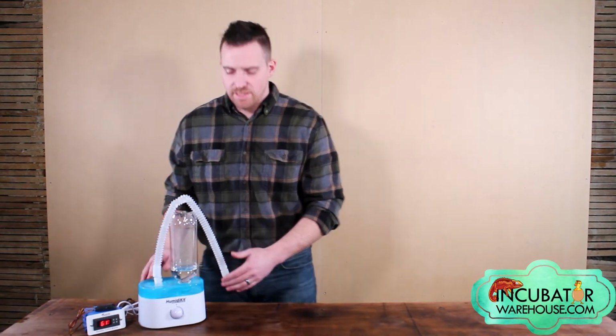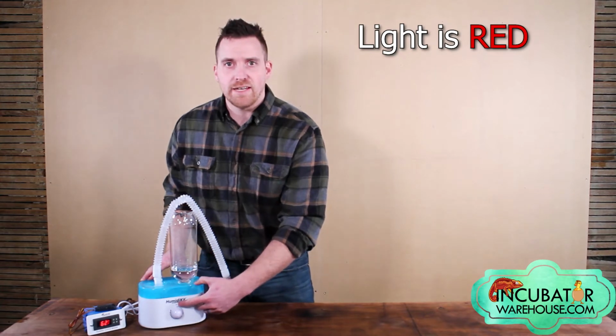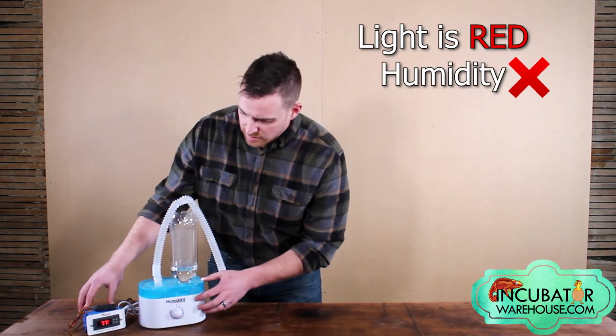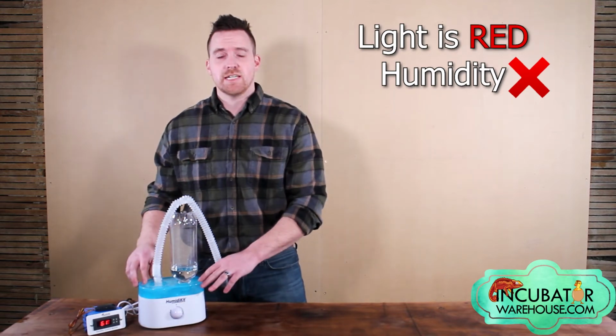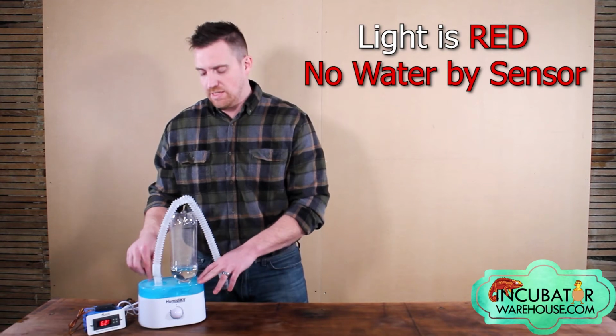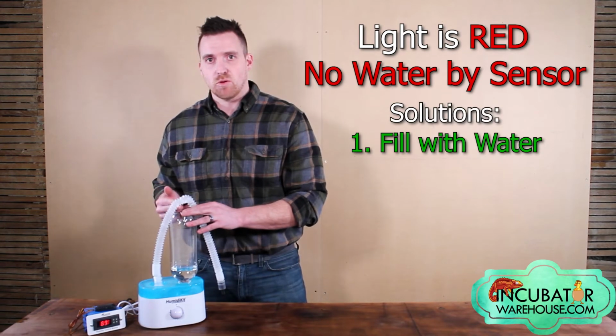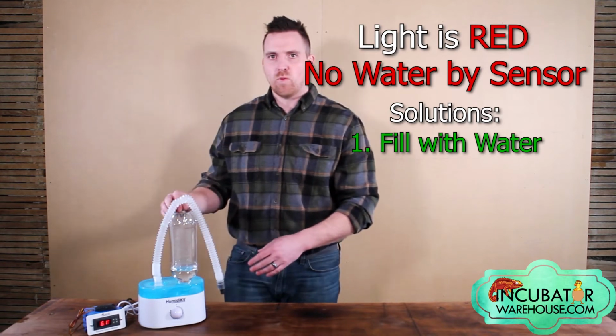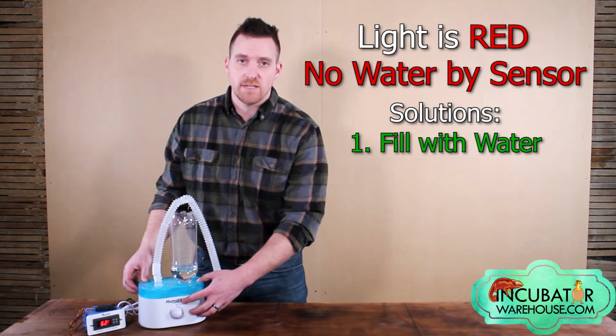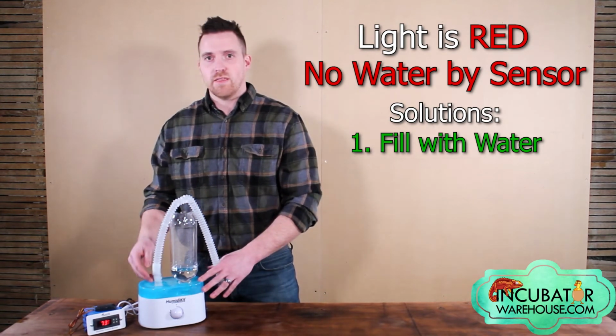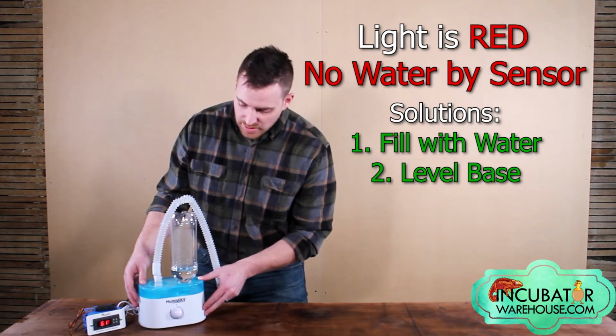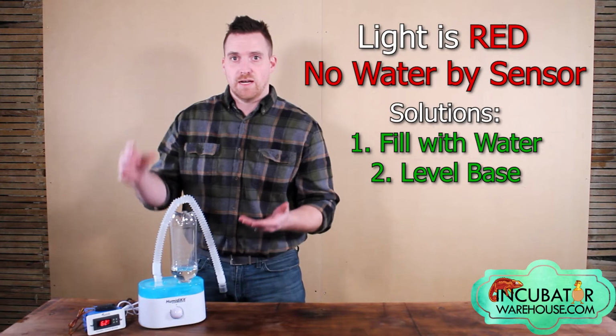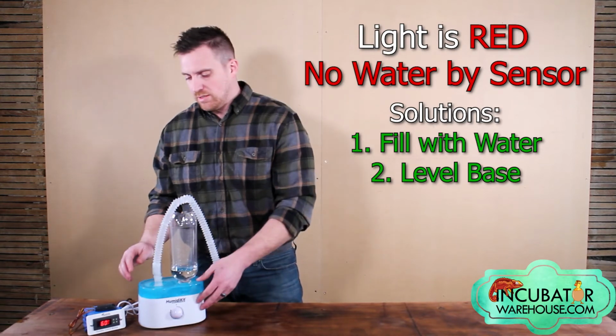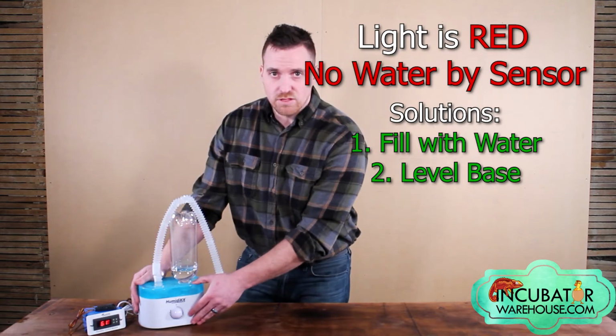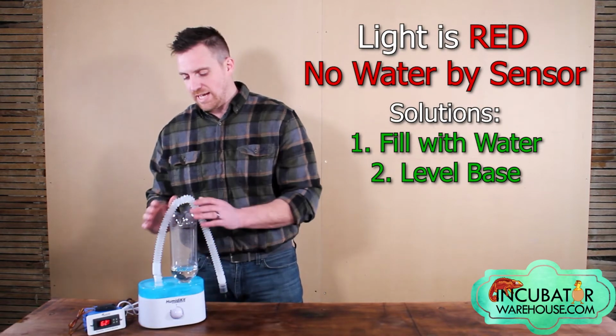Now, another problem that we sometimes encounter is that the Humidikit light indicator will be red and no humidity will be producing. The module is on and the light is red. This usually indicates that the base thinks that it is out of water. It might actually be out of water, at which you would just add more water to your bottle and continue using it. But if you have water inside the base and the light still says that it's red, there's a couple other things that could be causing this. One of them could be that the Humidikit base is unlevel, causing water to shift away from the float valve and tricking it into thinking that there's no water in the base. One simple solution is to make sure that your base is on a flat level surface and that the water level is also level on the inside.